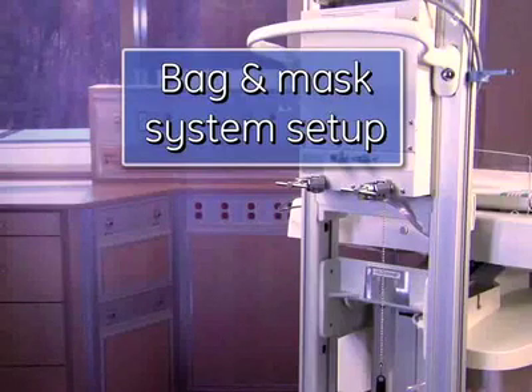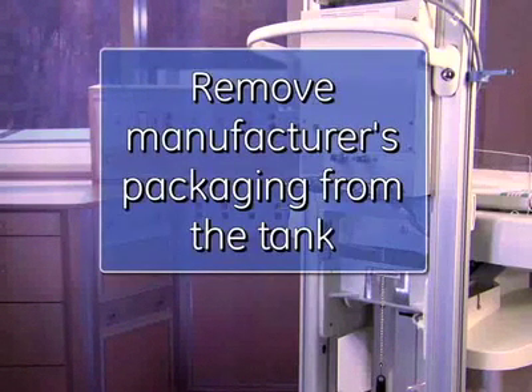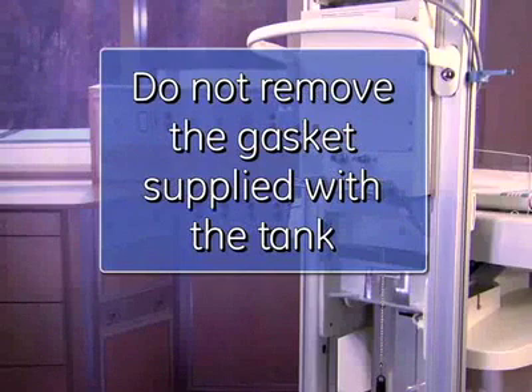Setup for the bag and mask resuscitation unit begins at the back of the unit by attaching the gas supply. If you would like to use a tank gas source, ready the tank by removing any manufacturer's packaging, but do not remove the gaskets supplied with the tank.